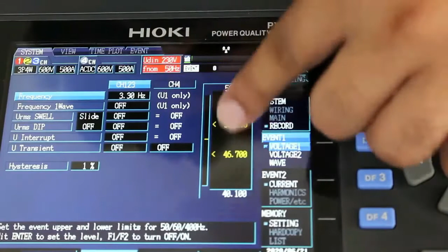And then you can mark the swells and dips, interruption, transient, hysteresis. If I press DF2 again, it will show RMS high, RMS low, RMS sense, peak, DC discharge, THD, voltage component, reverse phase unbalance, zero phase unbalance. All these kinds of things I can mark for the voltage anomalies.